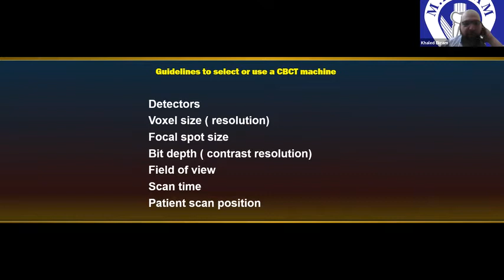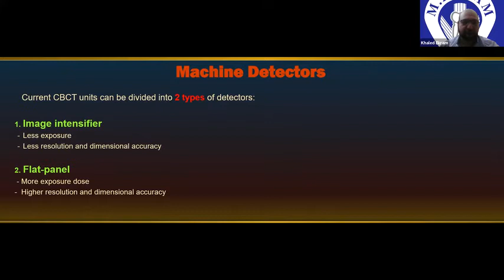First is the machine detector. We have two types of detectors. The image intensifier is a little bit old, and not a lot of machines have this type of detector. Image intensifiers make less exposure, but give less dimensional accuracy and resolution. On the contrary, the other type, the flat panel detector, gives more exposure and higher resolution and dimensional accuracy. And the increase in the exposure dose is not that significant.